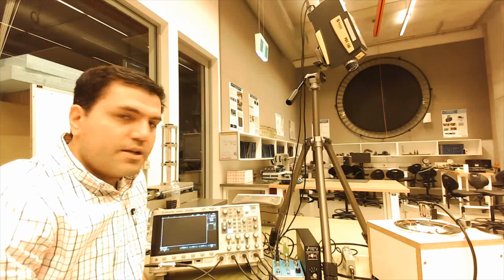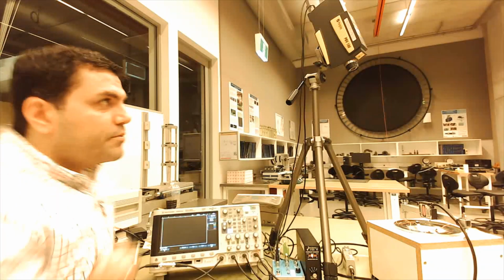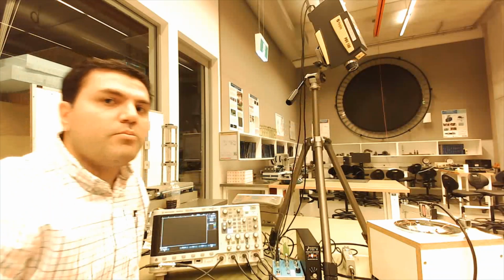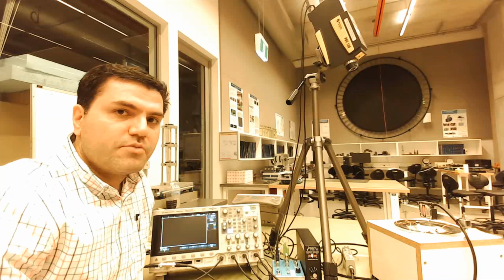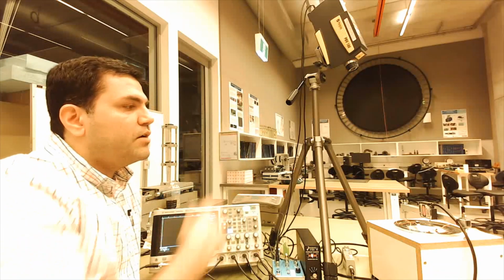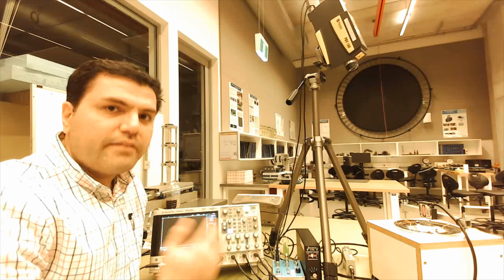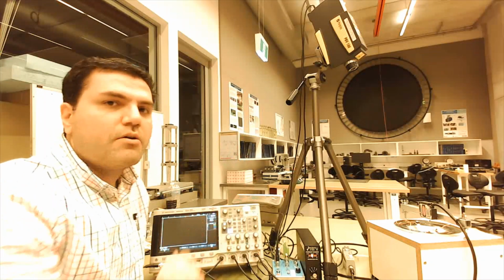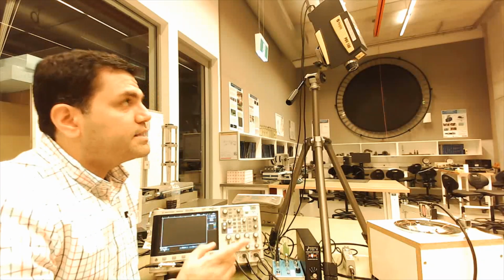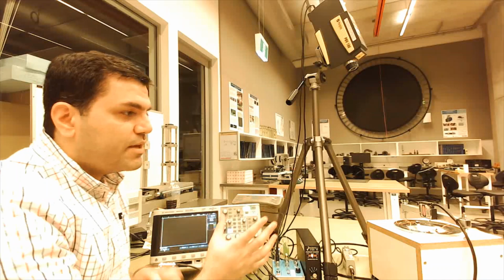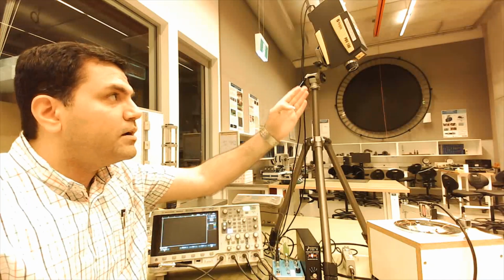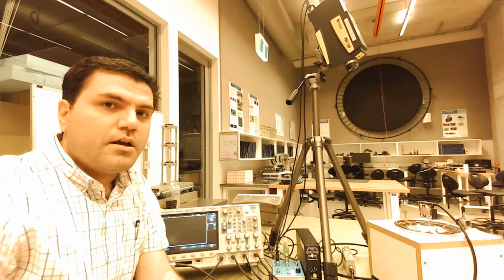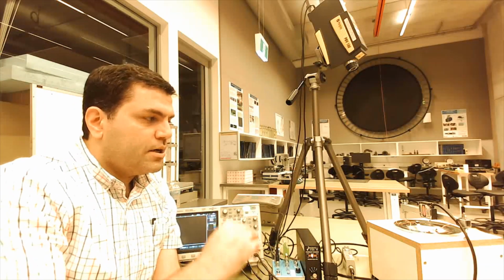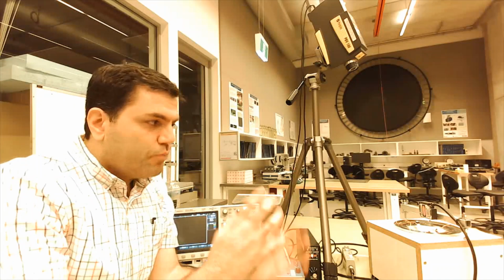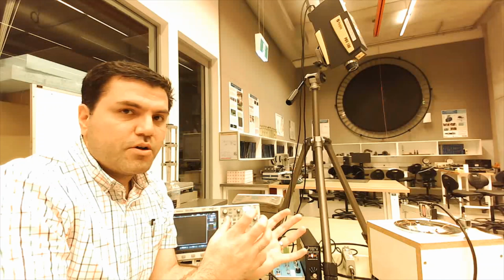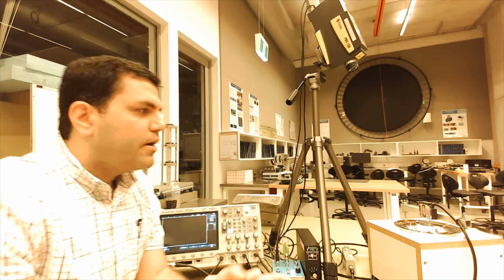The next type of transducer which we've got here is the LDV. Basically this transducer here is a laser Doppler vibrometer, which works on the principle of Doppler shift, and its output is also voltage, which goes directly into our oscilloscope here. We have tried our best to set up the experiment in a way that the laser beam of the LDV focuses on the same point as the displacement sensor. So they are both collecting the response of almost a single point.